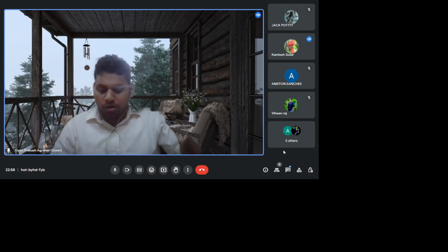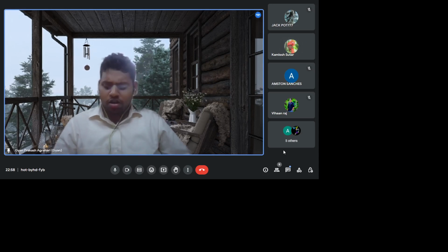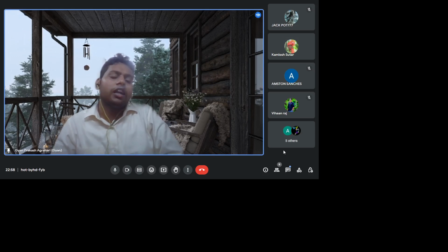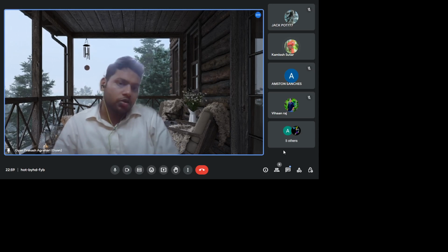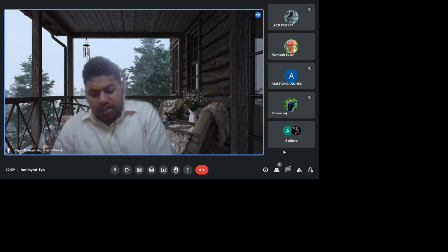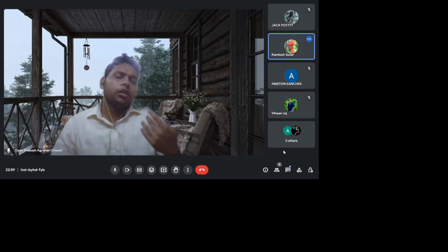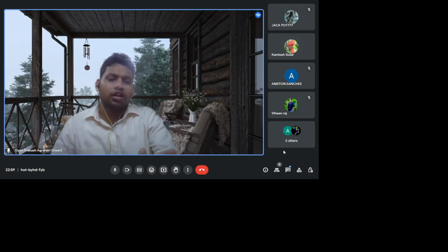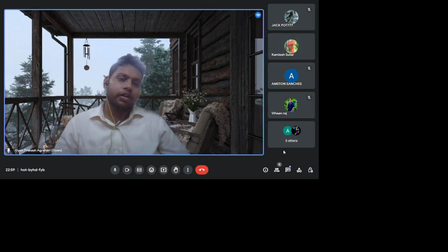Now we have the low water level shutdown. It is a float in the steam drum, used to indicate the level of water in the boiler. It is an alarm and trip. First it will alarm and then it will trip, shutting down the boiler. Optionally, a fusible plug can be used instead of it.